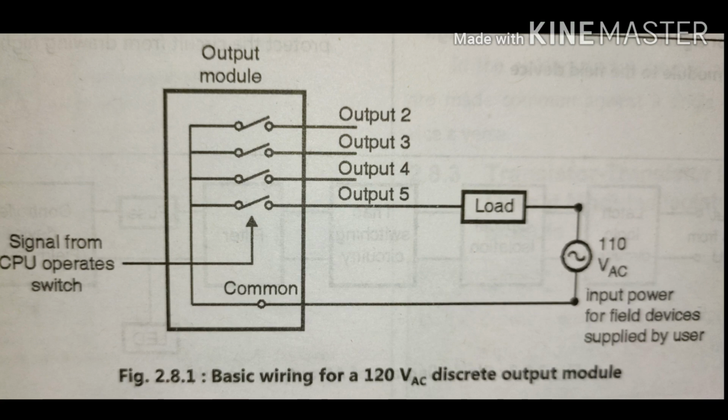Output modules are classified as discrete, analog or specialty. They also vary in switching voltage and configuration. There are a number of ways to get information from the CPU's output status file to common hardware field devices. First, the discrete output interface module provides a method of getting a discrete or digital signal out of the PLC to control discrete field devices. Second, ever-changing signals like temperature control, or a 4 to 20 milliamp speed reference of a VFD, variable frequency drive, can be interfaced to the PLC using an analog output module.